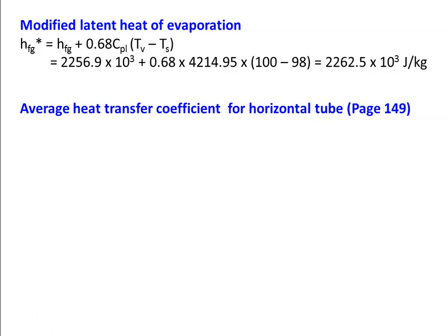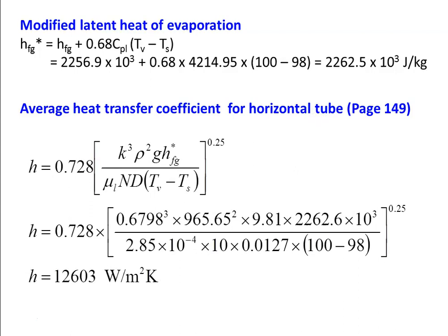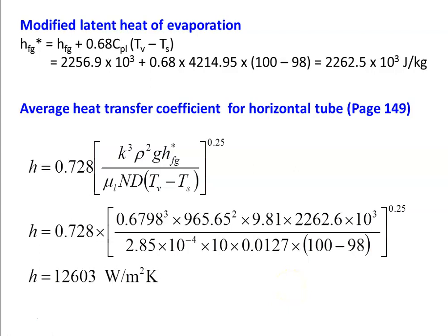The average heat transfer coefficient for horizontal banks of tubes uses page 148, equation number 3. The only difference from the single horizontal tube equation is that the denominator includes capital N — the number of arrays of tubes. The correlation is H = 0.728 × [K³ × ρ² × g × HFG*] / [μ × N × D × (Tv − Ts)]^0.25. Substituting all values and calculating, h = 12603 W/m²·K.